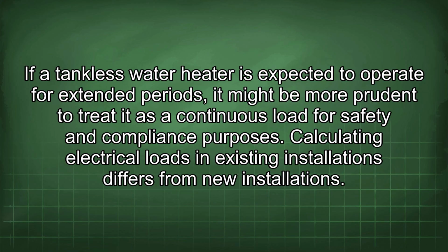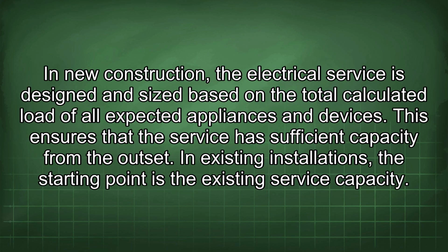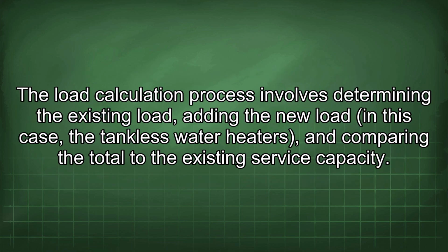Calculating electrical loads in existing installations differs from new installations. In new construction, the electrical service is designed and sized based on the total calculated load of all expected appliances and devices. This ensures that the service has sufficient capacity from the outset. In existing installations, the starting point is the existing service capacity. The load calculation process involves determining the existing load, adding the new load, in this case, the tankless water heaters, and comparing the total to the existing service capacity.